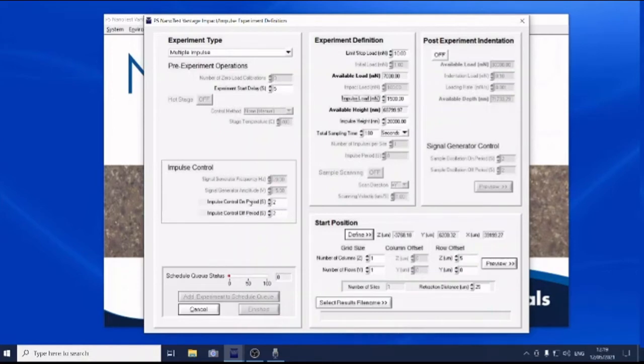So they're both set to 2 seconds. What that means is that the probe will be released and be in contact with the sample for 2 seconds, and then the probe will be removed from the sample for 2 seconds. That will take place repeatedly for the duration of the test, which we set here, total sampling time. Normally our tests are between 2 and 10 minutes, something like that. For this demonstration, we'll keep it to 180 seconds, so 3 minutes. And the final thing of significance, perhaps, is the acceleration distance. We normally set that with micro-impact testing to 20 microns. You can set it to longer or shorter, depending on what you want to achieve, but typically we use 20 microns.